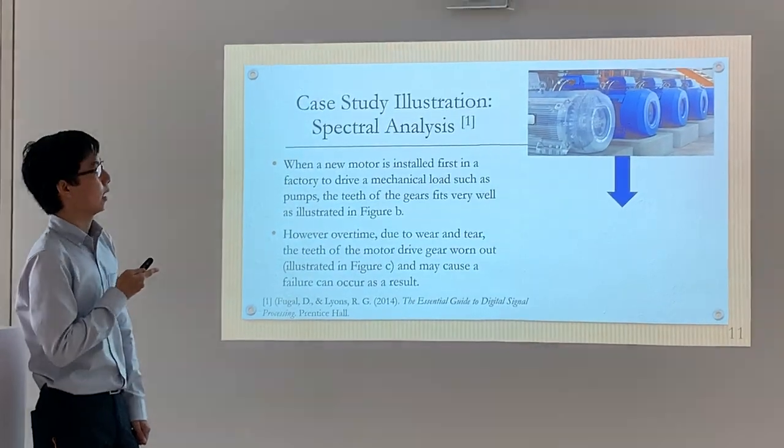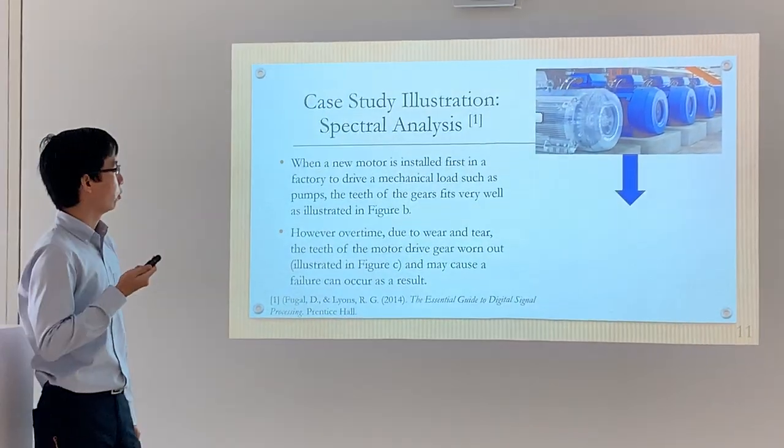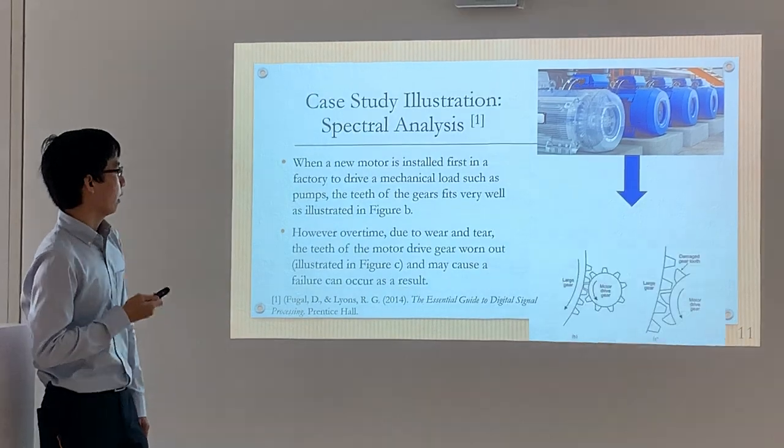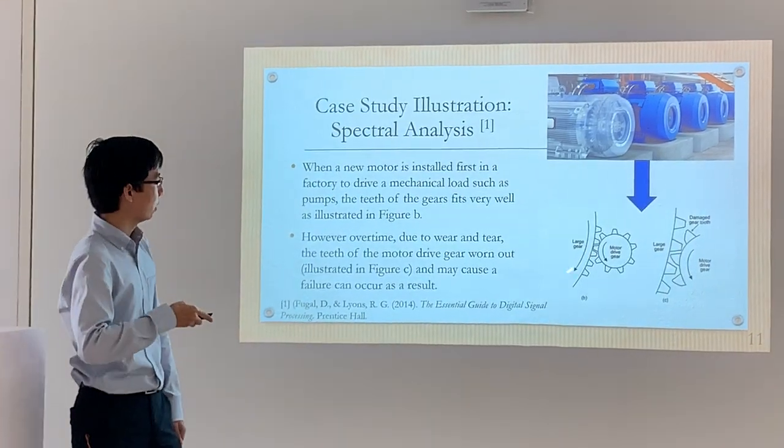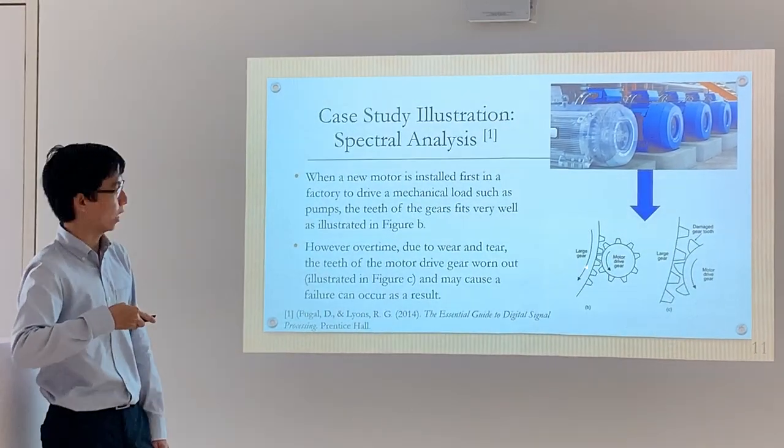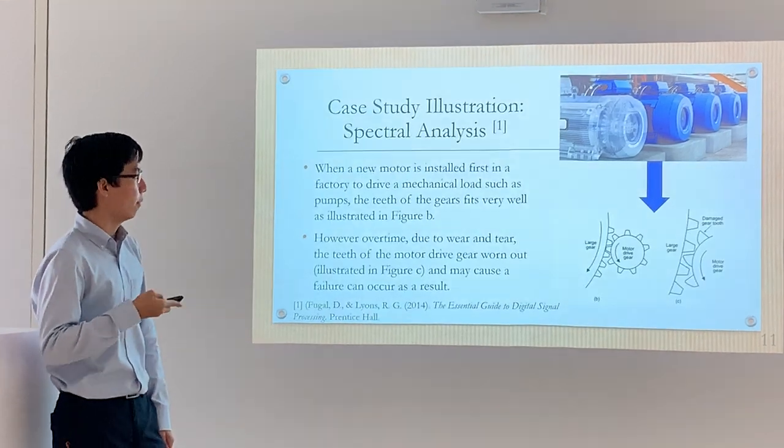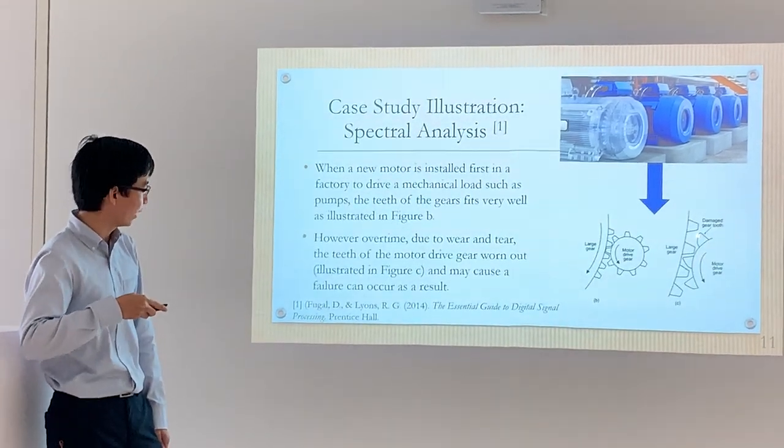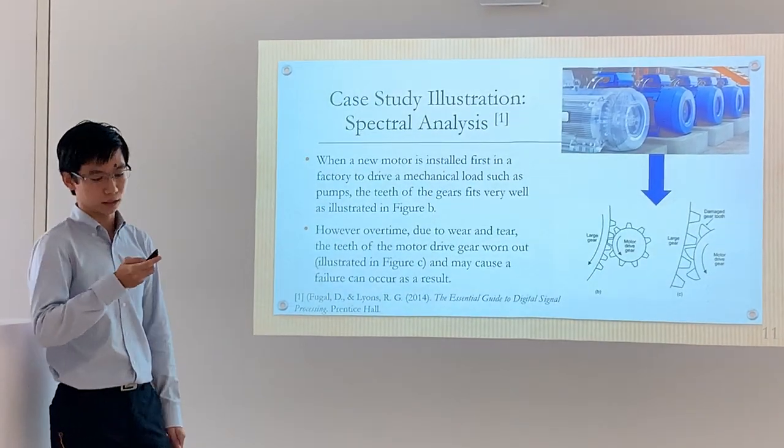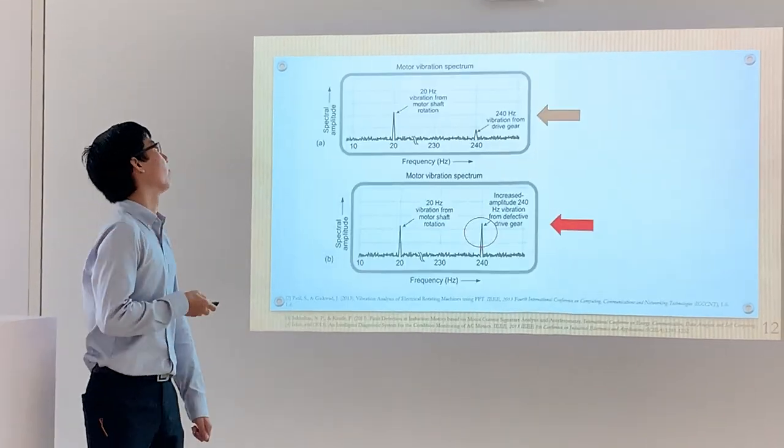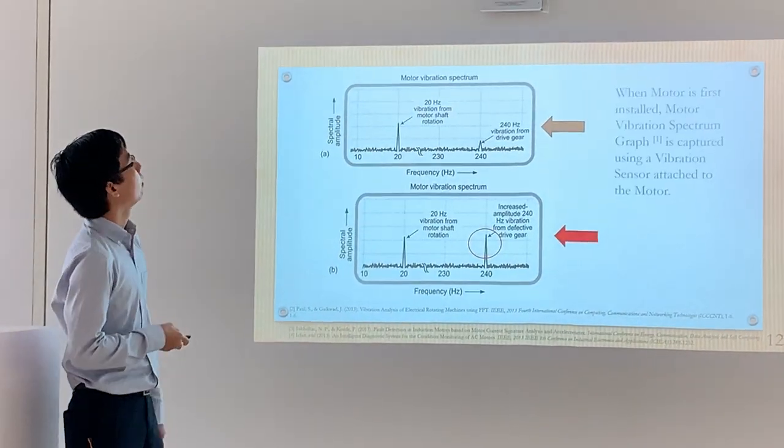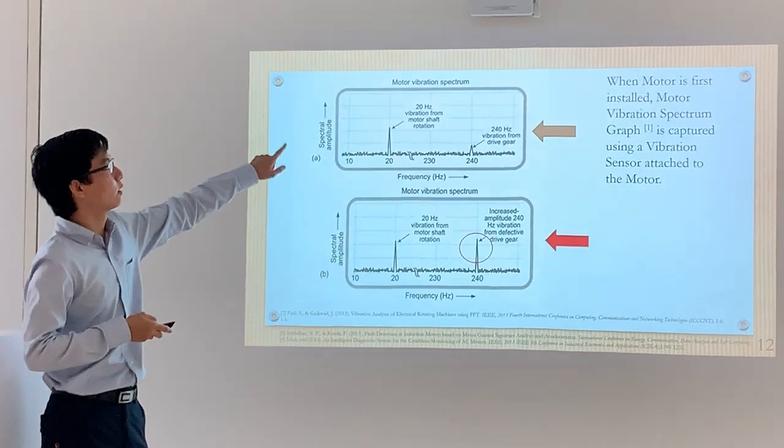Let's look at this case study here where we have a motor just newly installed on the factory floor. In the second picture, you can see that the motor drive gear meshed very well with the large gear. But over time, you can see that the gear tooth gets damaged and may cause a failure.